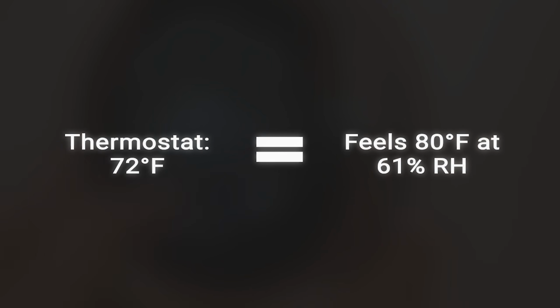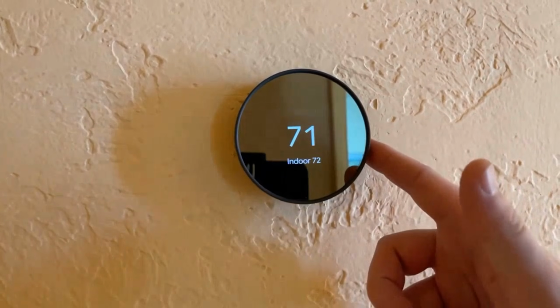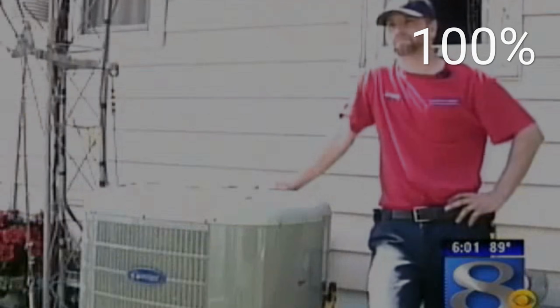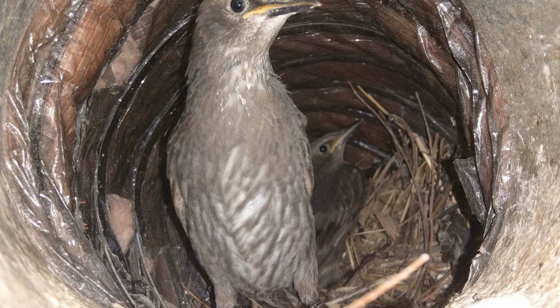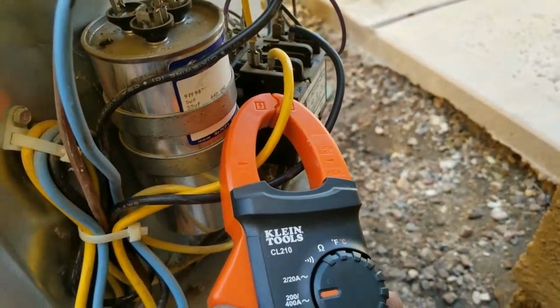Your thermostat reads 72 degrees, but your body feels 78. You lower the set point to 70. The compressor runs even longer. The coil reaches its dew point and freezes over. Ice forms on the evaporator. Airflow drops. The compressor works harder against the restriction.